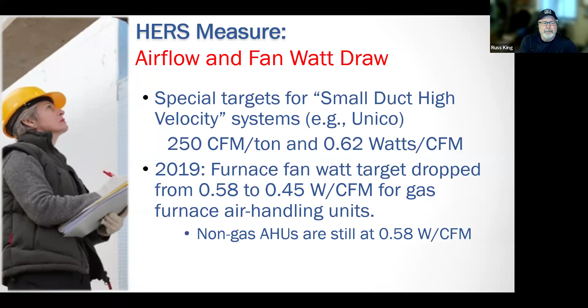Got a question. Is the CFM per ton not determined by the selected system capacity and the CFM settings? Let me go back a slide. This CFM per ton is determined by whatever they install. Okay. And it's based on the condenser. So if it's a 3-ton condenser, you take 3 times 350, and that's the minimum airflow they have to pass. So it's the installed tonnage that determines this.